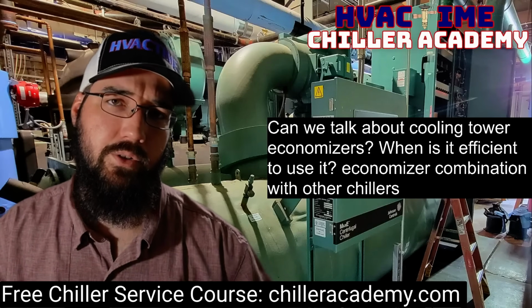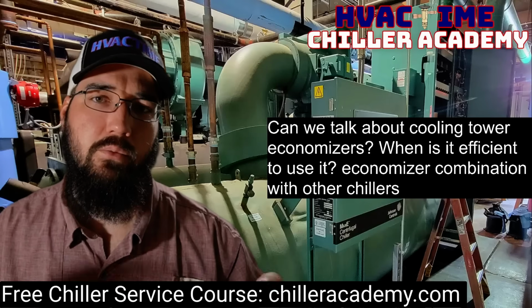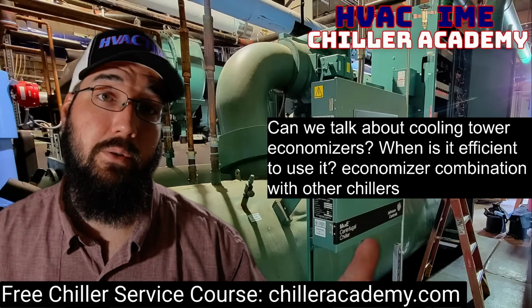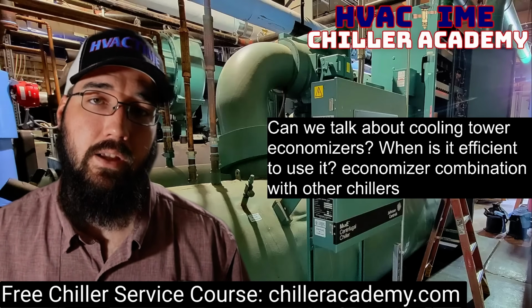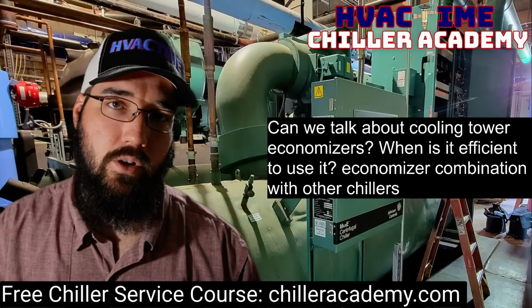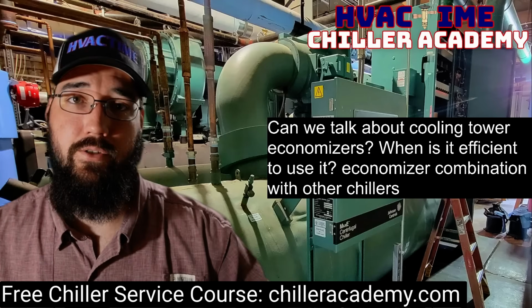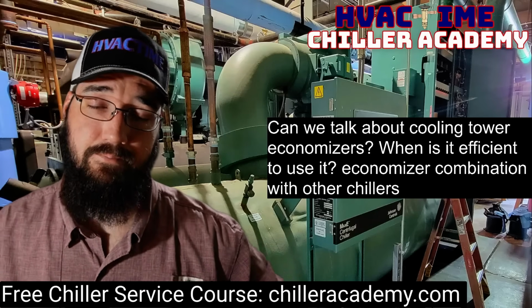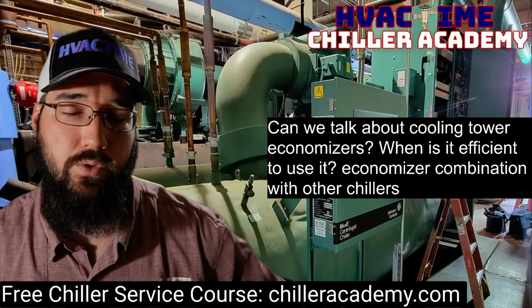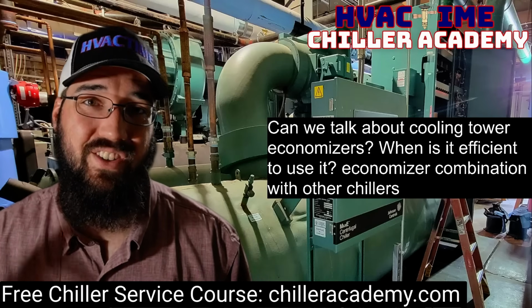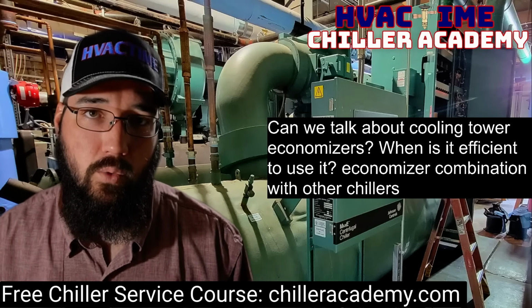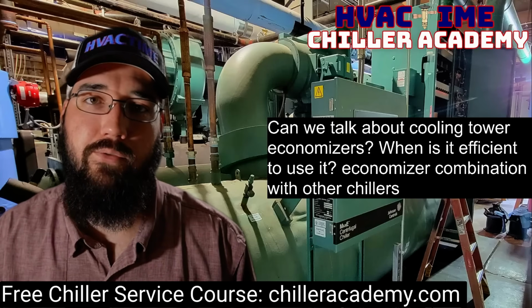In those situations, we don't want it to. But when we go into economizer mode, well, then we will actually divert to bypass the chiller typically, and then the condenser water will flow through one side of the heat exchanger and the chill water loop through the other side. Once the plant switches modes, the condenser water set point will be lowered to around, say, 40, 45 degrees.